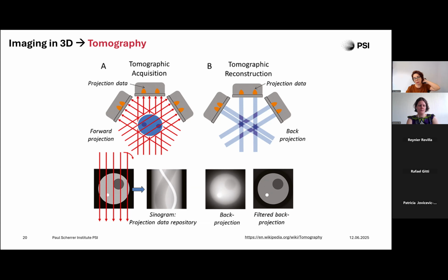By summing all of those back projected, filtered profiles, the overlapping contributions reinforce the true structures and cancel out any blur, and yield sharp, quantitative cross-section information, or let's say linear attenuation coefficients, which are linked to the material properties of the object.